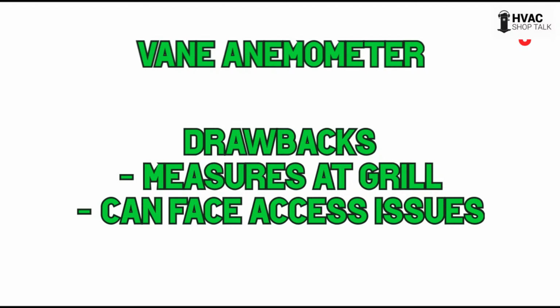Measuring at the grill, why is that a drawback? Well, the big drawback is the duct systems are not perfect. So if you have 80 foot of ductwork coming from that grill over to the unit, I bet it leaks. And you don't know how much it leaks unless you've done some sort of duct blaster test, which is not service tech land. Then you're going into I'm building for performance guy. You've left service tech land.